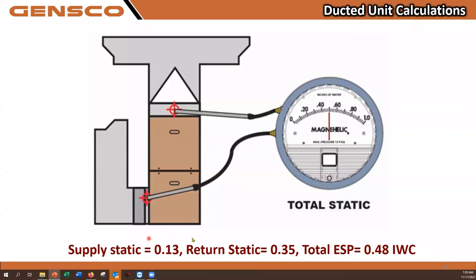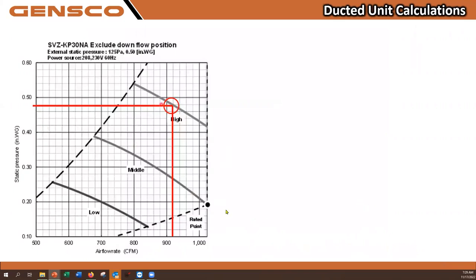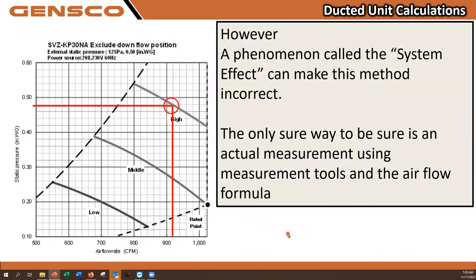In this example, our supply static was 0.13. Our return static was a negative 0.35. We add 13 to 35. This is where our total external static of 0.48 we used in the blower chart example came from. Plot that again on my chart, and it says about 920 CFM. But again, the system effect can make this inaccurate. But if you're just trying to get a quick measurement, this ballpark will be probably sufficient.